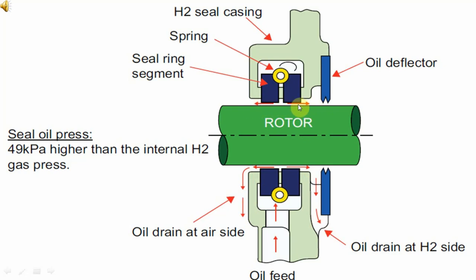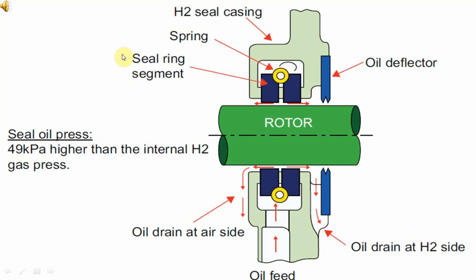This oil forms a film which is sealing the hydrogen inside the generator, and at the same time this oil film is preventing ingress of atmospheric air into the generator. We can also see the spring which is holding the seal ring segment on the rotor shaft.